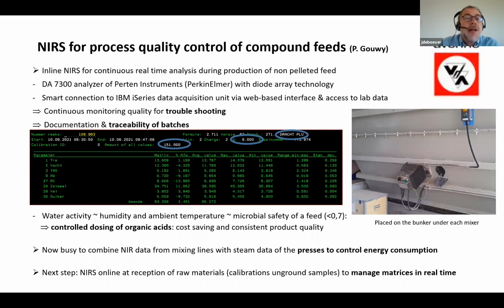Last, NIR is used for process quality control of compound feeds, for example, in Van den Avenne, where they use NIR in line, where the instrument is mounted on the bunker under each mixer, and they use this instrument for troubleshooting, also for giving documentation on their batches. But interesting is that they measure water activity, a parameter which is important for the storability of the feed, and so they can dose organic acids during the process, and this controlled dosing saves money and provides a consistent product quality.